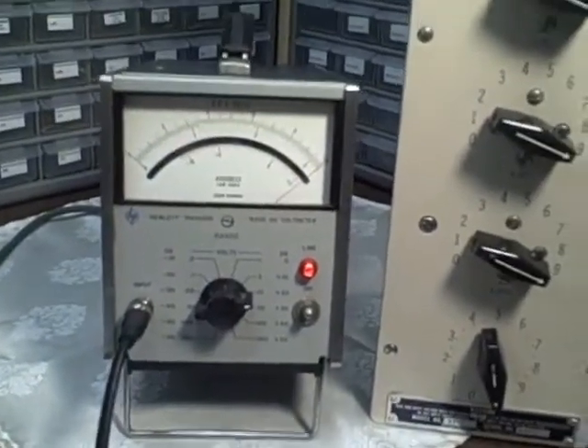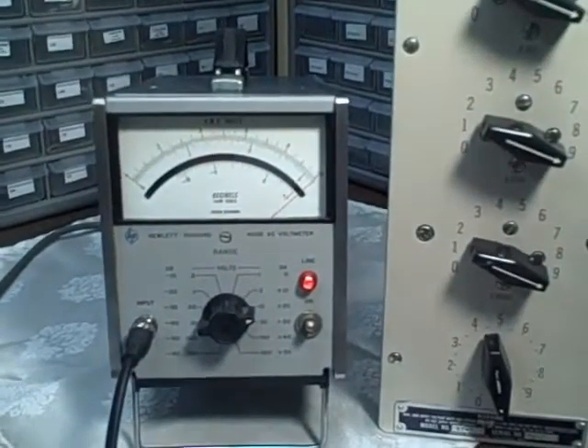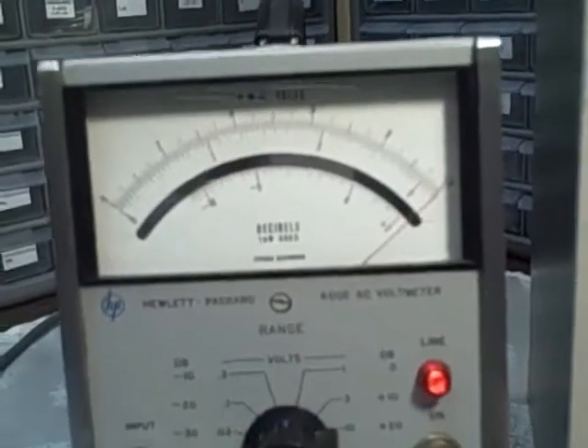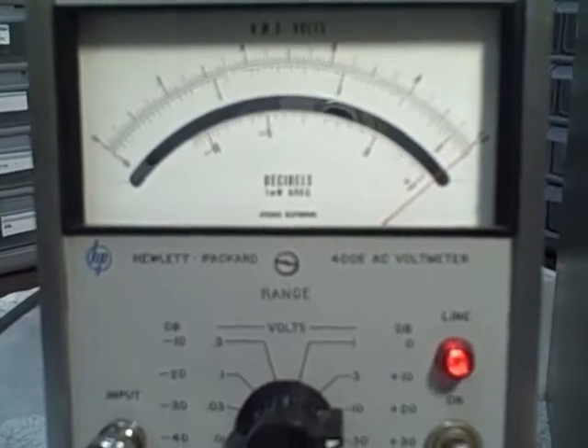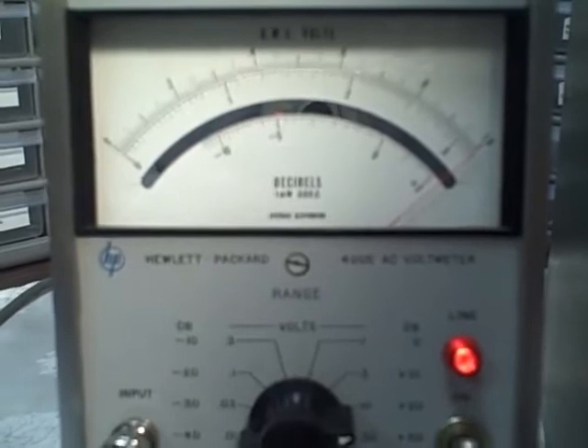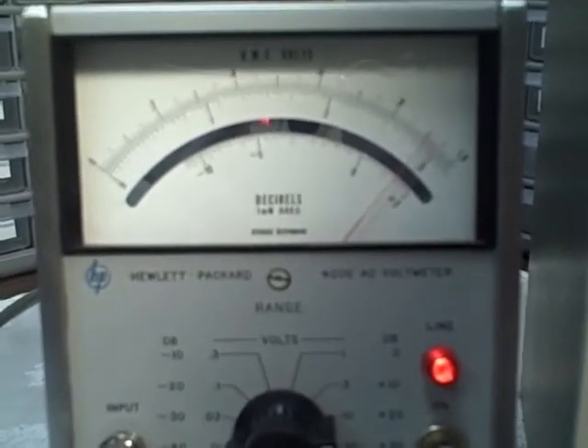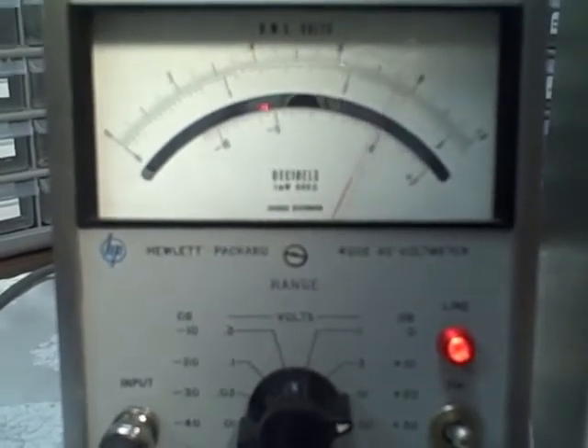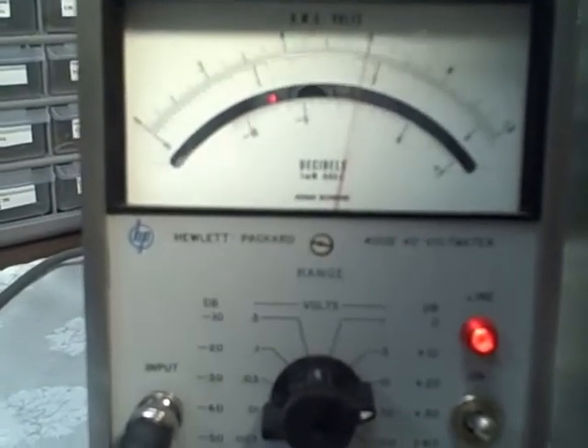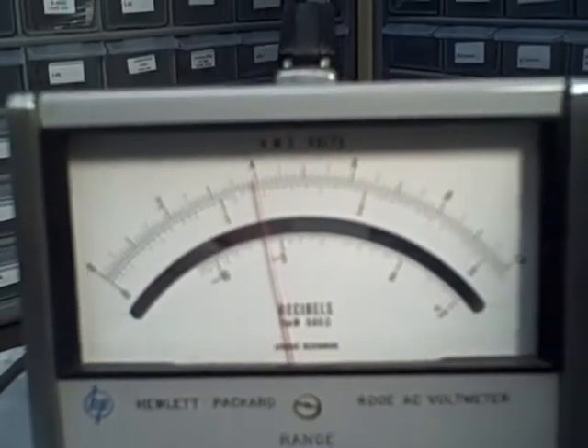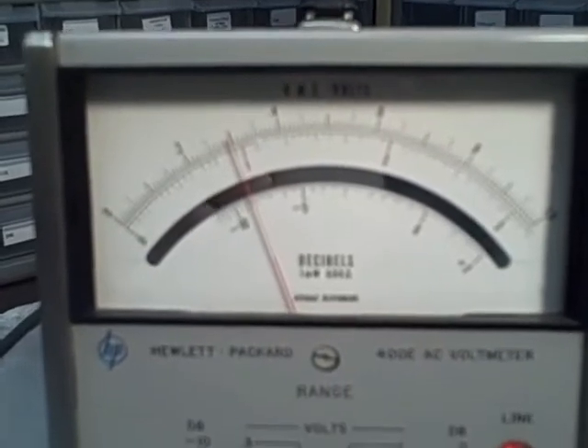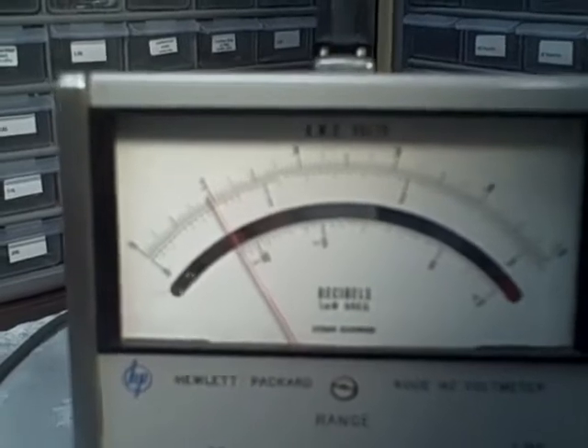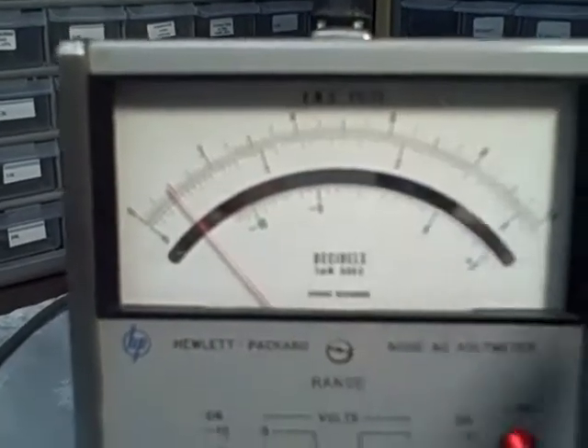Right now I'm reading on the 10 volt scale, a full scale reading of 1, so that'd be 10 volts. I'll do my best so you can see what's going on here. Now let's dial in 9, 8 - there's 0.8, 7, 6, 5, 4... sorry, my arm is in the way of the light. 3, 2, well let's leave it at 3. Okay, we'll take it down one. There's 1, that's 2, and here's 1. Alright, so we've traversed the whole scale, and all the steps were perfect.